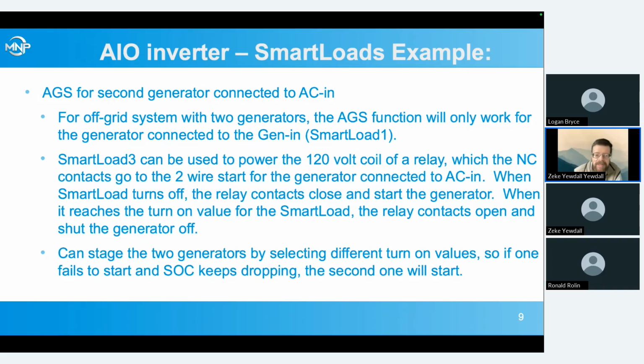So essentially, we can have the settings for our smart load control when that second generator turns on and off, and we can even pick, say, different turn on and turn off settings for the two generators, so that if one fails to start and it passes the start setting for that one and keeps dropping, then maybe we catch it on the second one. So we can kind of have some redundancy there. And that's a way to use that other smart load, not really to control a load, but to do something else that we want to change based on battery state of charge.